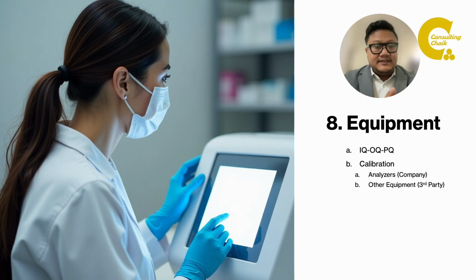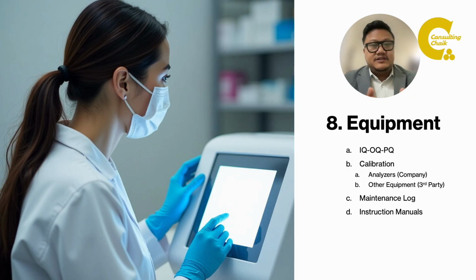So for analyzers, you have the company specified calibrations done, and for the other equipments like centrifuge or micropipette, you have a third party calibration. Then you have your maintenance log for each analyzer that is required, and then you have your instruction manuals in place. So to elaborate it, first the IQ, OQ, PQ.